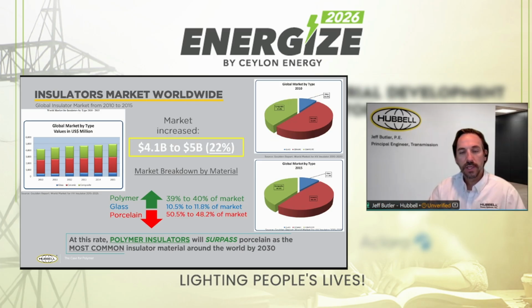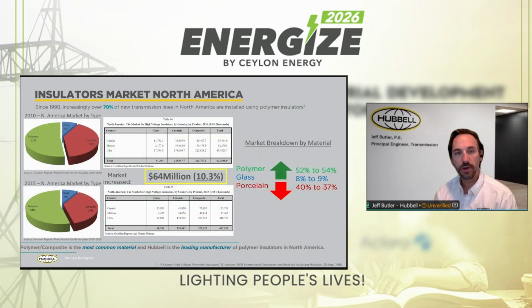At this rate, here in the next number of years, by 2030, we would expect that polymer insulators will surpass porcelain as the most common insulator material that is used throughout the world. And this is for new constructions, new insulators, new installations. And then that market growth during that time went from 4 billion to 5 billion, so a 22% market growth during that time from 2010 to 2015. And just as a point of reference, here in North America, that top line, since 1998, over 70% of new transmission lines in North America are installed using polymer insulators.